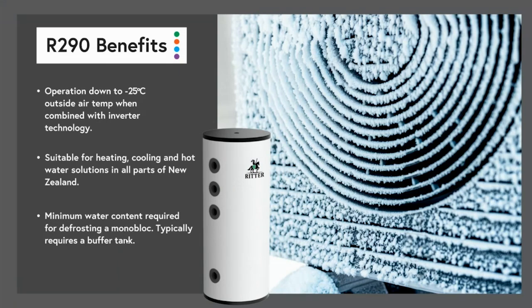Right, R290 benefits again. So the next operational benefit of R290 is its ability to operate down to very low air temperatures. So an R290 heat pump can run down at negative 25 degrees C. Why? How can it do that? Well, it does that because of that very low evaporation temperature of sort of less than negative 40. So even at negative 25, it can still transfer energy into negative 40-degree refrigerant and get a result where it starts to give up its heat as a vapor because of the evaporation process.